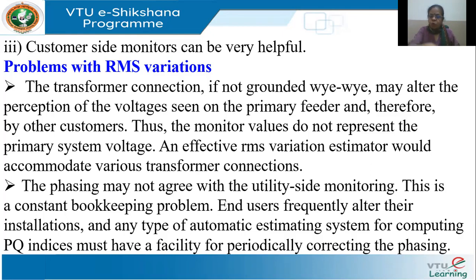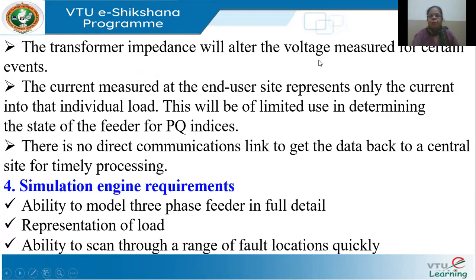So the utility side has placed their monitors and developed a model, everything assuming lighting is in phase B and drives are in phase A. Now, after some years, the industry infrastructure changes and they find it's not convenient and they shift all the lighting load to phase R. So there is a change the utility doesn't know about. So this should be periodically checked. This is one issue that can happen.